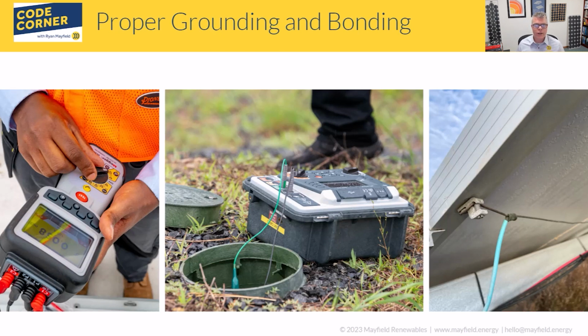If you're at a multi-megawatt array that does have a substation, it's very likely that you have earth wells, and you have to go in and start verifying and checking those on an annual basis. So those are just things to be aware of. If it's a standard commercial industrial site, it's probably above and beyond what you would be doing in terms of checking those exact requirements. But the earth tester is there, especially if you're having problems, if something is coming up and you need to look at that.